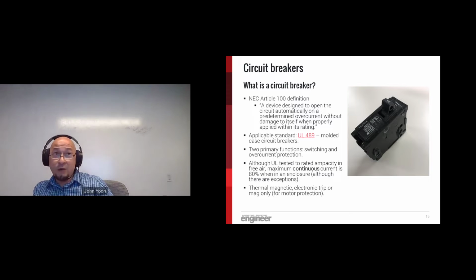Let's move on to circuit breakers now. Again, we have another definition from the NEC that you can read. Based on this definition, a circuit breaker can be opened and closed against all magnitudes of current up to its short circuit rating, basically acting as a switching device. The UL standard that applies to most common types of circuit breakers, molded case circuit breakers, is UL 489. Again, the NEC doesn't necessarily dictate how quickly a device must interrupt that abnormal flow of current. That requirement is defined by that UL standard. One important point is that when UL tests circuit breakers, they are tested for their rated ampacity in free air.